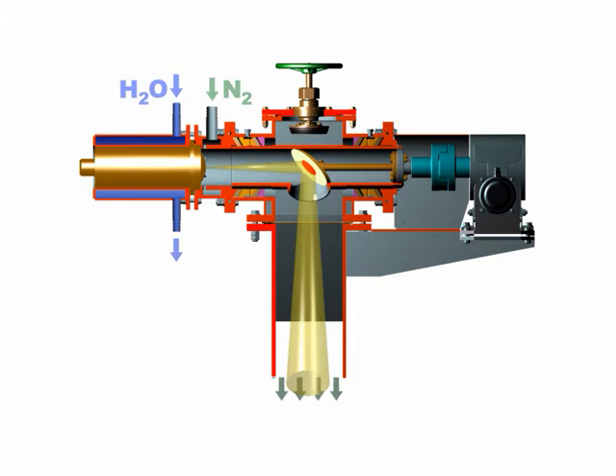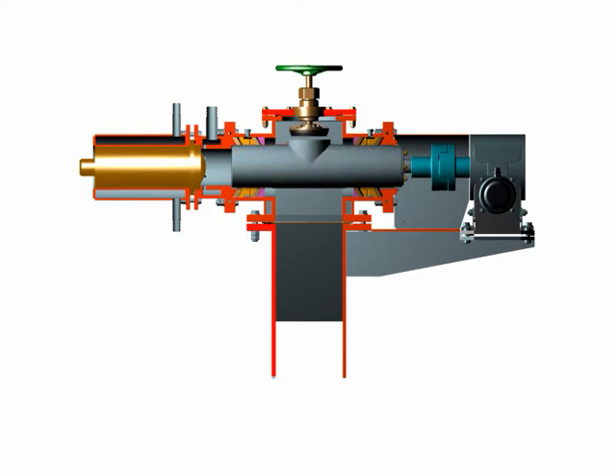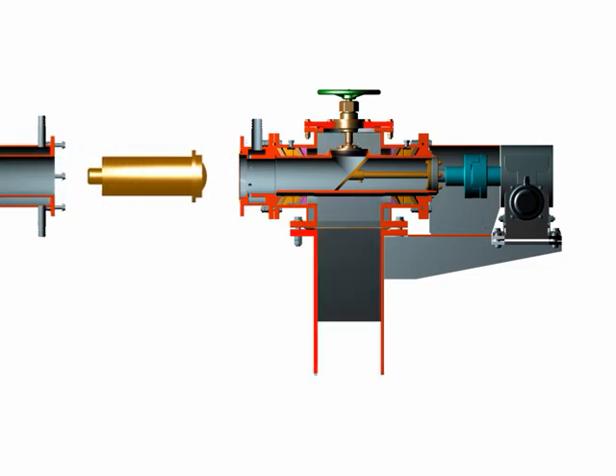Maintenance. Profile meter is designed in such a way as to make it possible to maintain and repair it without having the blast furnace run disturbed. Radar and reflector actuator power supply are put off. Cooling water and nitrogen are put off. Slewing body together with the reflector are turned into the maintenance position.